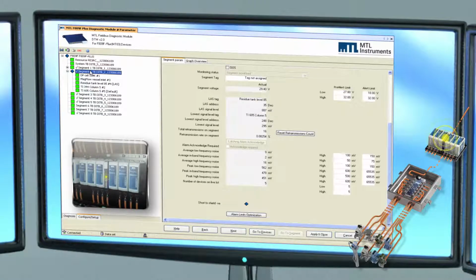The F809F+ can also detect short circuits between the Fieldbus plus or minus signal wires and the cable shield. Although the Fieldbus network is likely to continue to operate in the event of a first short circuit, a second fault could result in loss of a complete segment. Here, a short circuit has been detected between the Fieldbus negative connection and shield, and a maintenance activity should be initiated to trace the location of the cable fault.